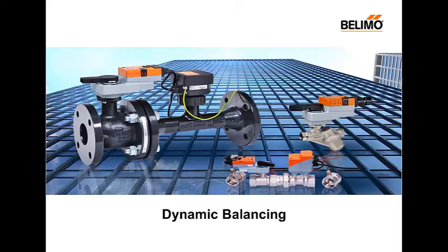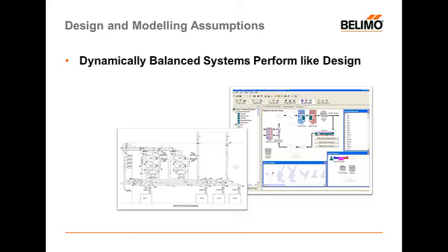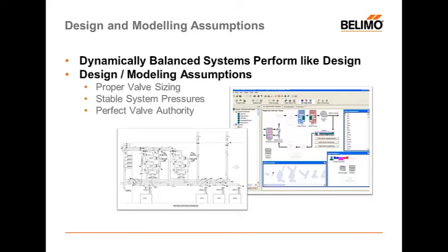Let's go ahead and take a look at what we mean by static balancing versus dynamic balancing and how each of them influences your hydronic system. As we get started here, it's important to point out that the majority of the energy modeling software that is available commercially assumes your system is dynamically balanced from a hydronic standpoint. And the reason that they make these assumptions, and assumptions is probably an unfair word, really what happens is that they ignore some of the points that become problematic in a statically balanced system.